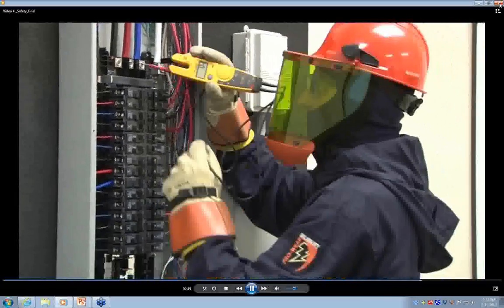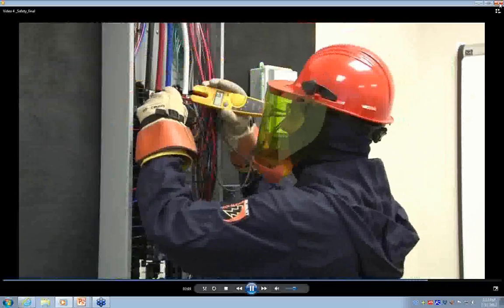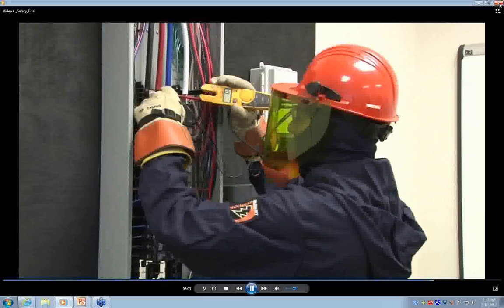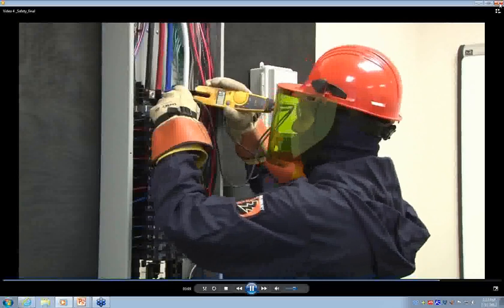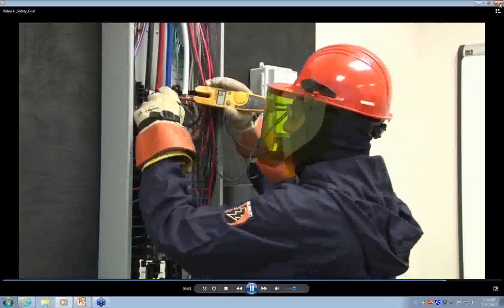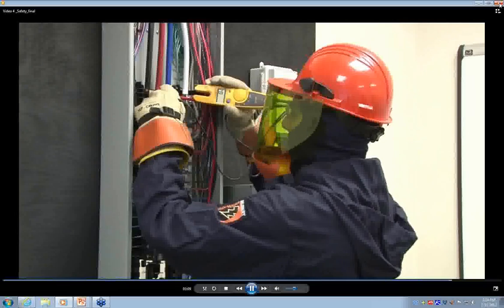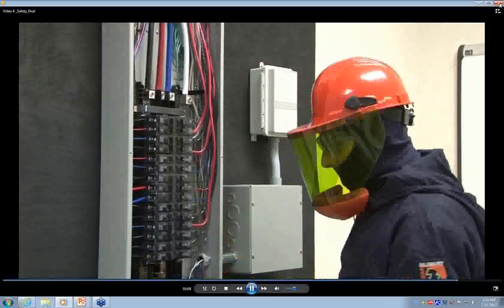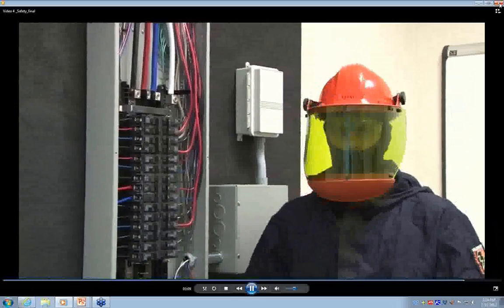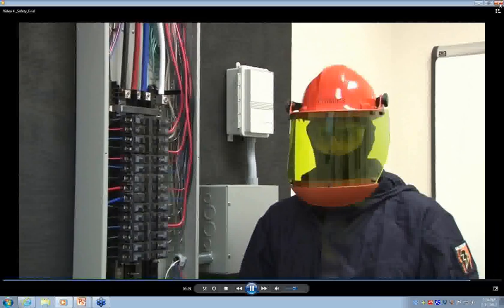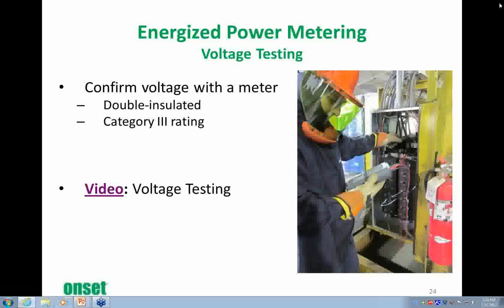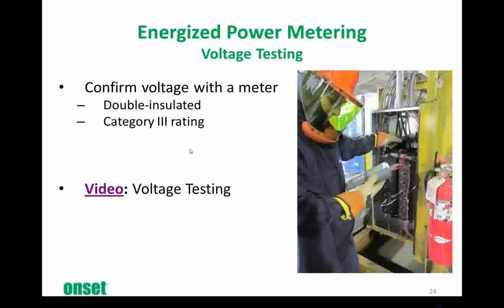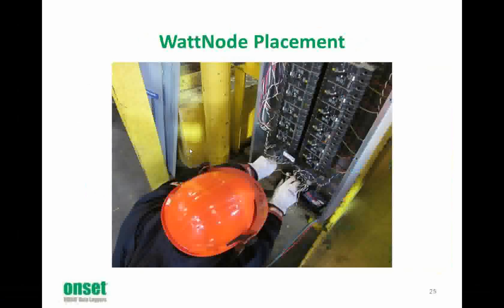We'll then check the voltage phase to phase, measuring the voltage between phase A and phase B, phase B and phase C, and phase A and phase C. For this, we should read approximately 208 volts. Once we've confirmed our voltage, we can now install our data logging equipment in the panel. Okay, so as you can see, that panel actually was not live, but I just wanted to demonstrate what it would be like wearing all of the equipment.